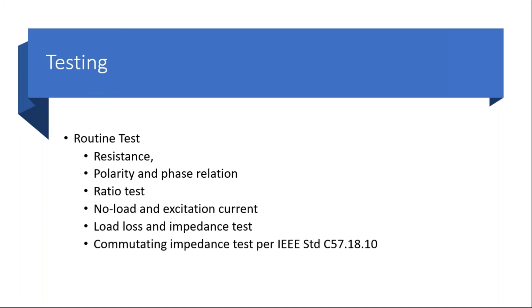But if you look at all these, ratio probably is one of the things. We talk about extended delta. It may not be possible to do ratio tests with the standard ratio meter. So from there, if the angle is plus 7.5 degrees, minus 7.5 degrees, which is very common for multiple pulse transformers, you have to use either an oscilloscope, or there are special meters which would measure the voltage and compare the numbers between secondaries and the primary. Also, it will give a phase angle between the wave shapes. And you would need a three-phase power supply to do this test. So those add some more complexity to the testing, but when you see the results, they would not show you a big difference from table to table.